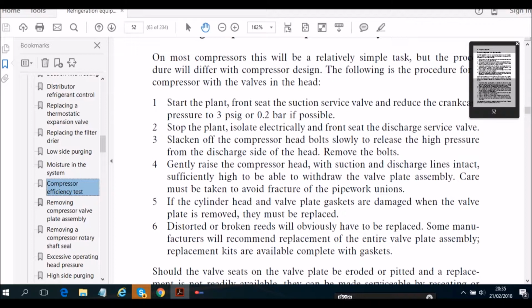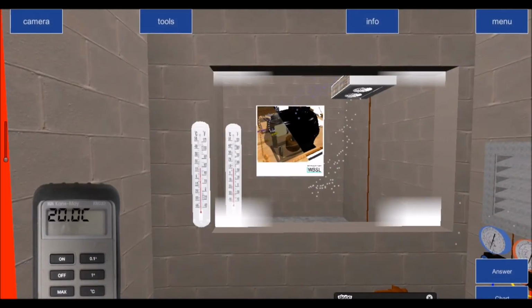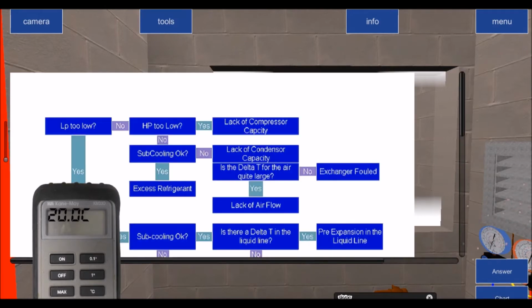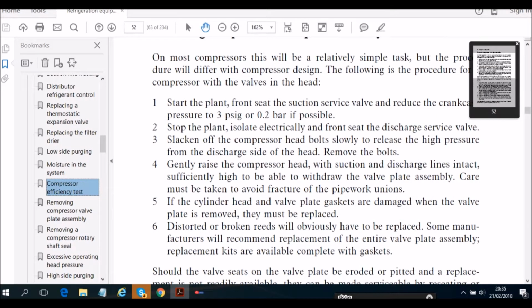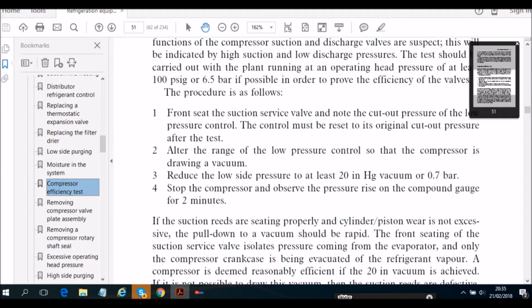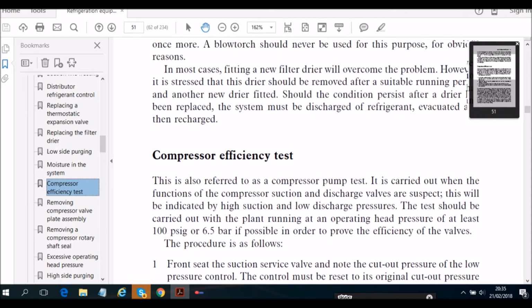You do not want the compressor to start up with a fully front seated discharge valve, because that discharge pressure will have nowhere to go, because you'll be blocking it from getting into the discharge line, and that will cause problems. It'll break your compressor up. It will certainly break valve reeds or burst a gasket or build up to head pressure in it, okay? So what I would suggest is, when you do fault number one, which is the lack of compressor capacity, then you go to the book and you have a look at the compressor efficiency test, and that will explain how you check out that the compressor is pumping properly, okay?